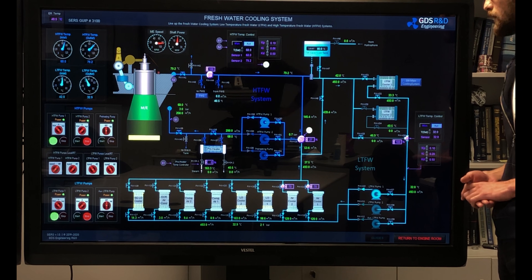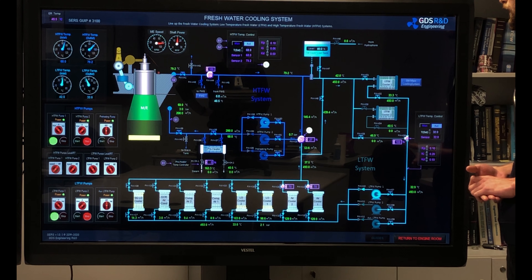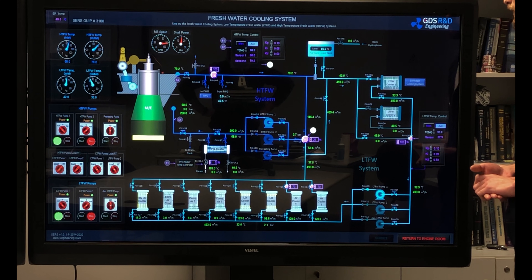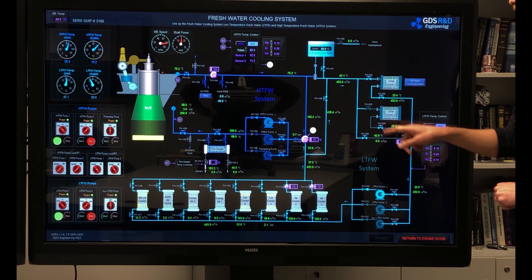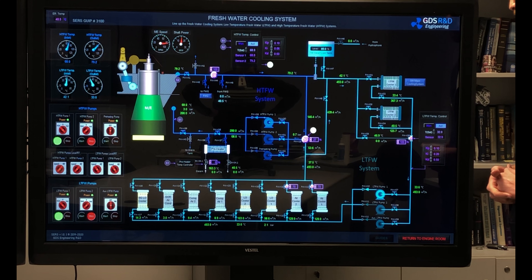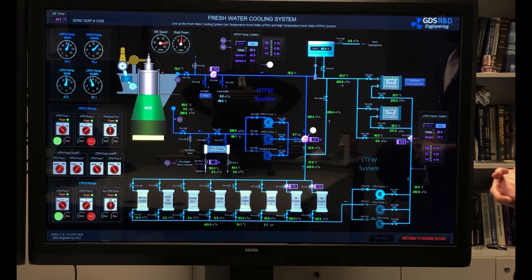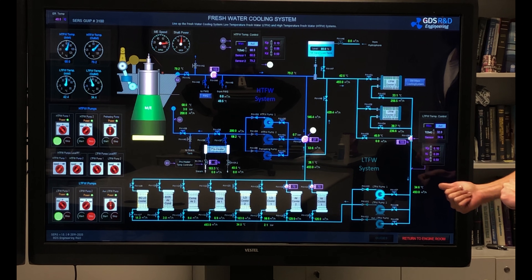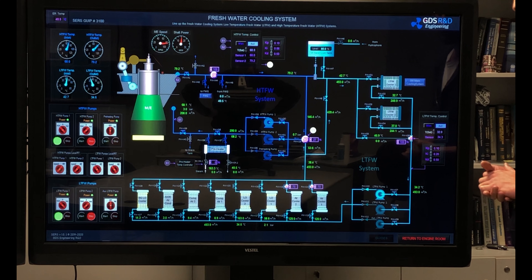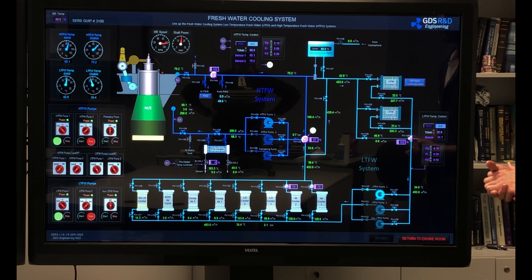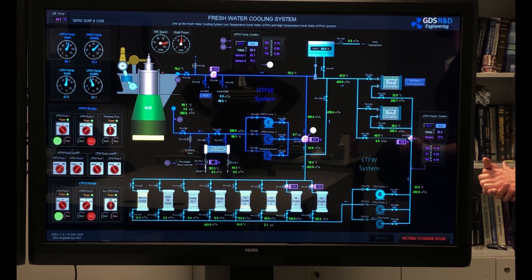Now I am feeding freshwater cooler number two with seawater and I am going to open the valves on the freshwater side. Here is the outlet valve and the inlet valve. The average temperature of the LT fresh water is dropping down, which is a sign that cooler number two is doing its job.